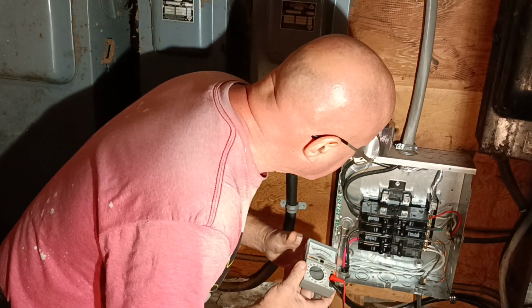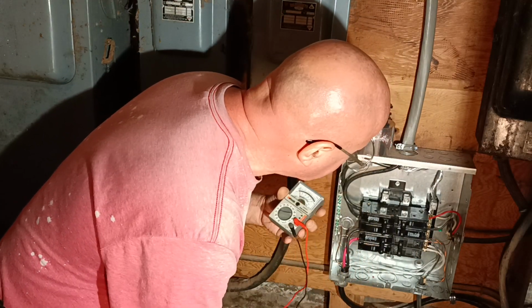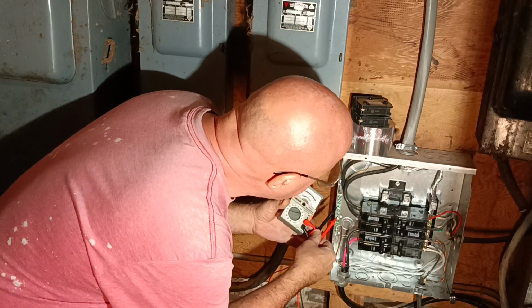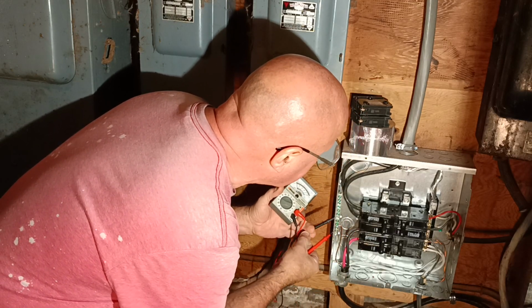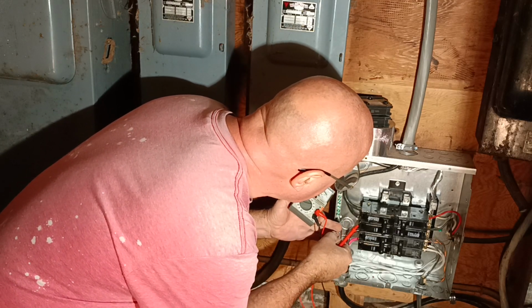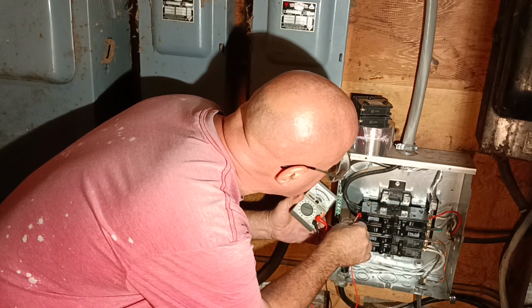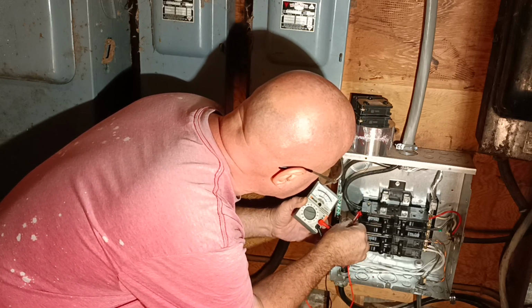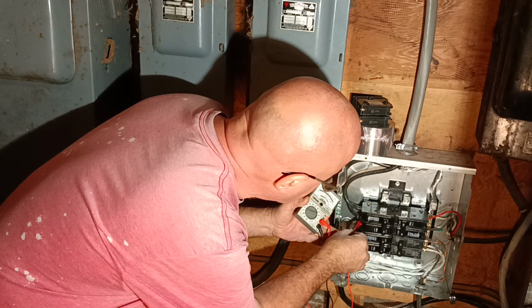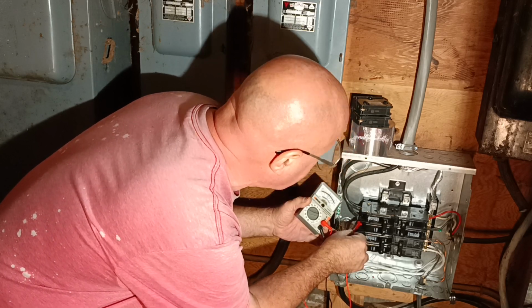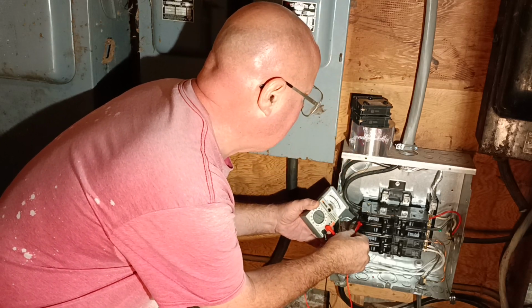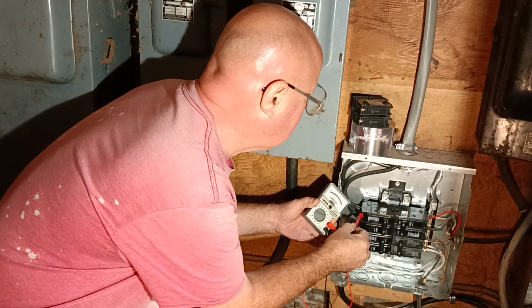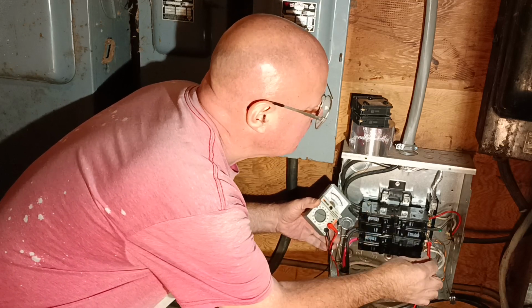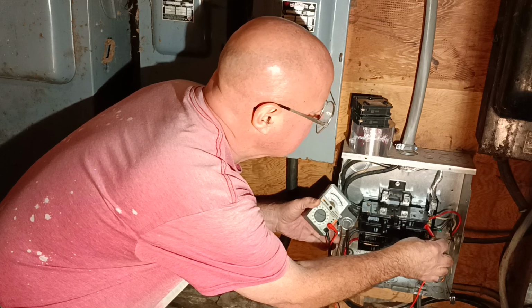Okay, so this is the 100 amp main, and we're going to see if we have 240 coming in. But I'm going to check each one to the ground. So I'll put my probe in here on the ground side. 120 volts, see how it's going up halfway? 120 volts, see it going up halfway there? Now this is the one we're questioning.